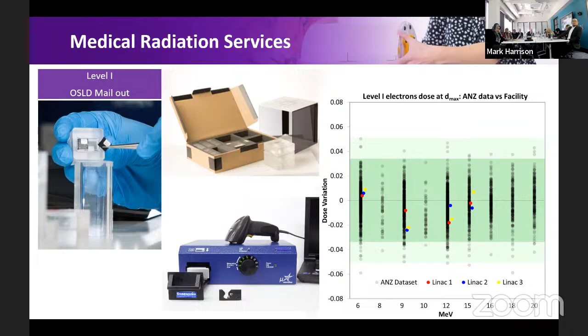The value of the system, particularly after you've been running for a while, is you end up with what we call a national data set, which means we have a very powerful set of data that covers every audit which has been conducted by the ACDS using the OSL system across all the Linacs in the country, across all the energies offered. And you can see there the 3 dots represent the 3 dose responses for 3 Linacs in the one facility. So you also get to have an idea about local spread within a given facility, as well as national characteristic. And what it means is that the ACDS doesn't only audit a facility for itself, it also compares it against every other facility in the country, and that creates a very powerful tool.